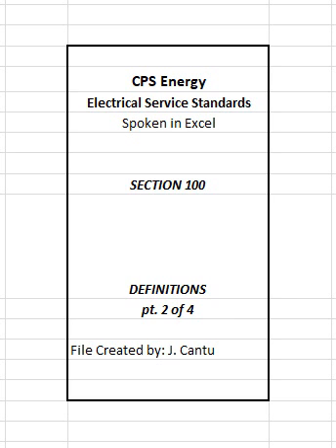Kilowatt, kW. This is an abbreviation for kilowatt, an alternate term for rating electrical devices. Generator sets in the United States are usually rated in kW. Sometimes called active power, kW loads the generator set engine. Kilowatt hour, kWh. This is a unit of electric energy. It is equivalent to 1 kW of electric power supplied for 1 hour.